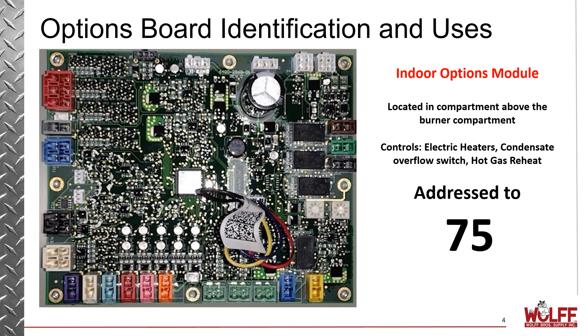Next is the indoor options module. This module is located in the compartment above the burner compartment. This controls options such as electric heaters, condensate overflow switch, and if you have hot gas reheat. This board needs to be addressed to 75.